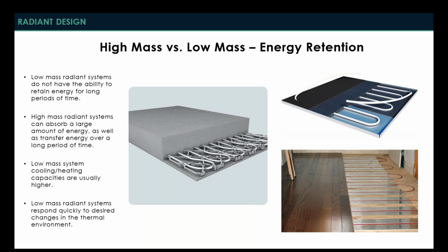Low mass systems for cooling and heating usually have higher capacities than a high mass system, and the low mass system is able to respond very quickly to changes in the thermal environment. That becomes very important when you're thinking about what radiant system might be right for a space. If we're talking about small conference rooms and closed office spaces, typically a low mass system is going to be a better option because it's able to react very quickly. If someone hasn't been in their office all day and then goes in and thinks it's hot and lowers the thermostat, a low mass system is going to be able to react quickly to that. A high mass system may not.